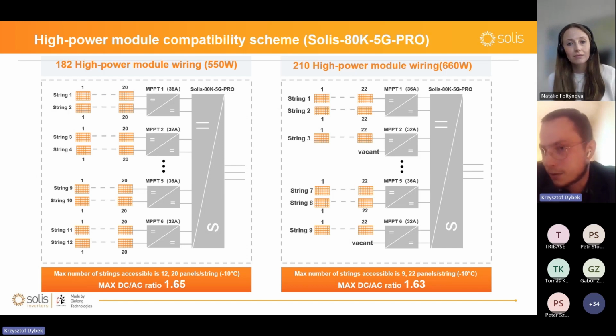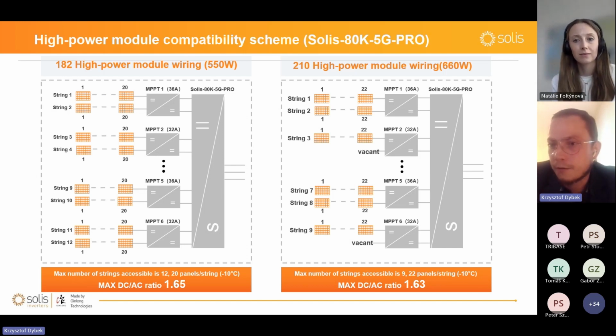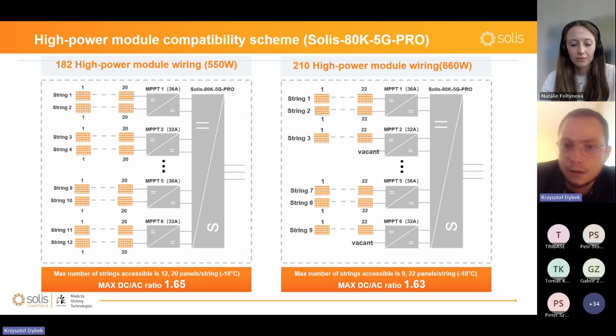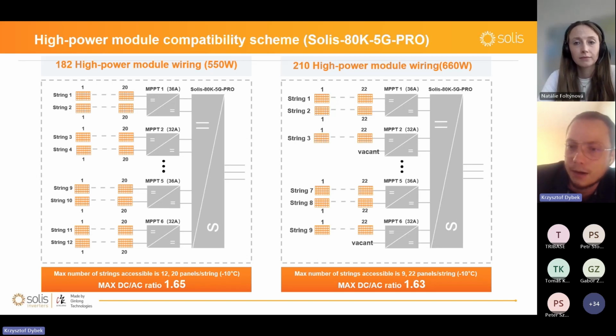So if you need to divide current between MPPTs, you need to have 18 amps per string in the first MPPT and 16 amps in the second MPPT. The third has 18 amps, followed by the fourth with 16 amps. So the conclusion is like this: if you use 550 watts modules, you can put the same number of panels per both inputs on MPPT. But if you use 660 watts modules, you can put 2 strings per higher current MPPT, but only 1 string on the MPPT with lower current, as you can't parallel strings if you don't have the same number of panels per string in one MPPT.